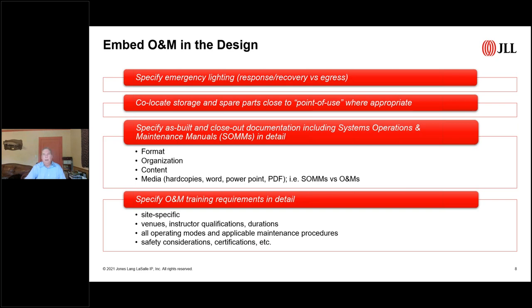From an operations and maintenance staff perspective, when the building goes dark because a breaker opens or there's a power failure, rather than exiting the building, they generally go to the source of the problem to make corrections. So certain rooms need full emergency lighting, not just a little bit of light, so they can work safely and resolve problems. Consider the lighting requirements in emergency situations.